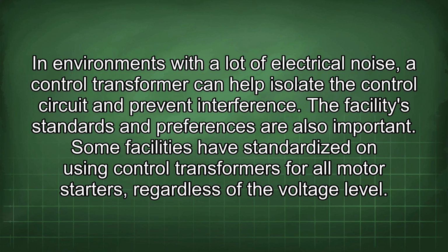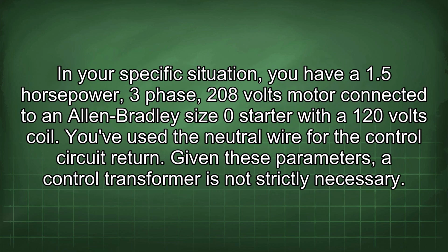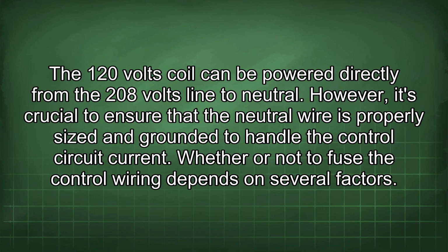Some facilities have standardized on using control transformers for all motor starters, regardless of the voltage level. In your specific situation, you have a 1.5 horsepower, 3-phase, 208 volts motor connected to an Allen Bradley size 0 starter with a 120 volts coil. You've used the neutral wire for the control circuit return. Given these parameters, a control transformer is not strictly necessary. The 120 volts coil can be powered directly from the 208 volts line to neutral. However, it's crucial to ensure that the neutral wire is properly sized and grounded to handle the control circuit current.